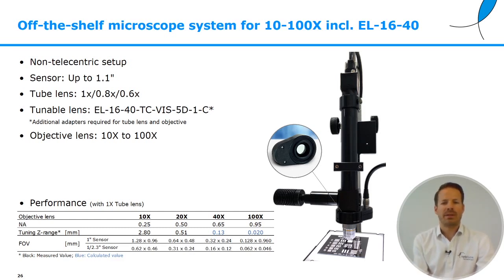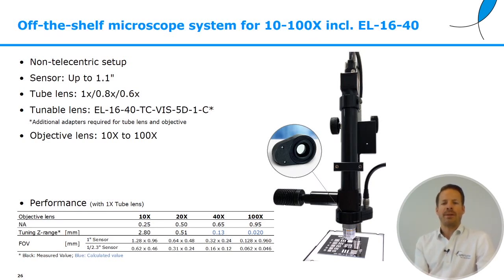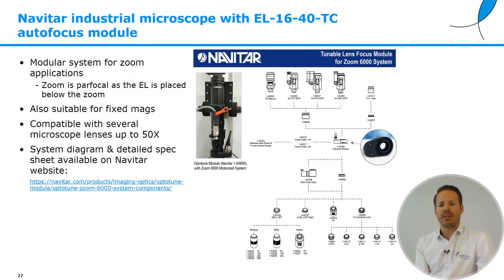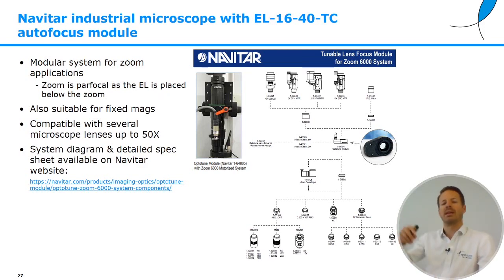Here's an example of an off-the-shelf system where several field lenses or objectives can be used — numerical examples up to 100x. We can fit our C-mount version EL16-40 lens for a fairly flexible design. Navitar has also introduced the EL16-40 as an autofocus module, paired with several field lenses or objectives and fitting with the Zoom 6000 system. Typically the liquid lens is placed below the zoom, which makes the system parfocal — meaning you do not change focus while zooming, because zooming happens above the liquid lens.